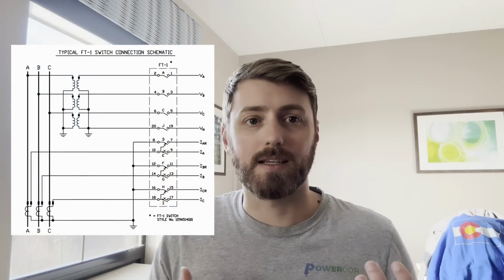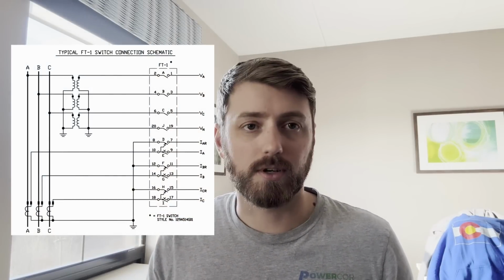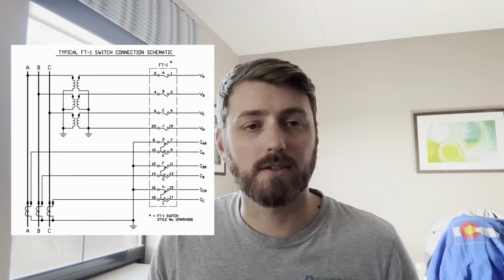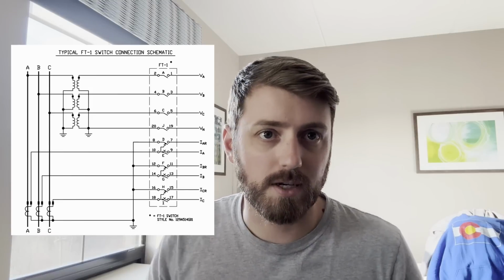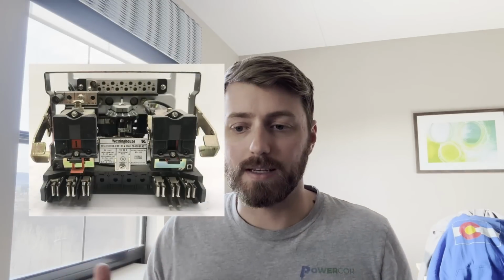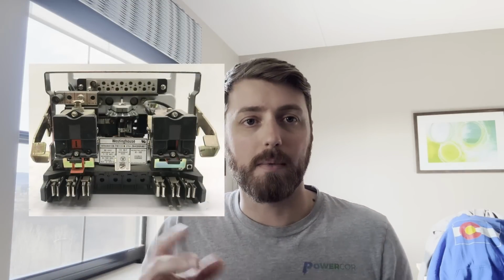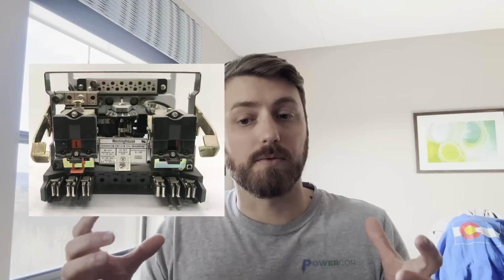These test switches were built directly into the FT style relay chassis, into the bucket that enclosed the relay, for connecting the CT secondary circuits, the voltage circuits from the PTs, and trip circuits from the switchgear or from the substation yard. Test switches allowed the relay to be completely disconnected for maintenance and testing by opening them up, and then you could slide the guts of the relay out.